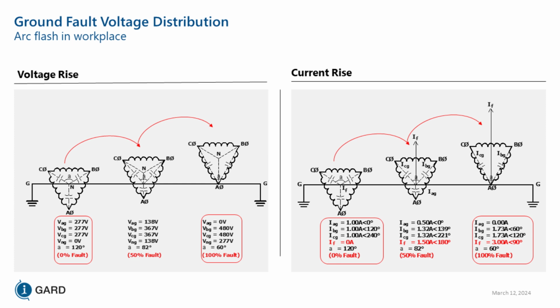Now, it's important to see in this particular diagram that we do not energize ground in an ungrounded system. You can still touch the enclosure. All we've done is shift the vector relationship with respect to ground, such that B phase and C phase are now 480 volts to ground instead of 277 volts to ground. So we just shifted the apparent neutral up 277 volts due to the ground fault. And the current you can see here is the capacitive coupling. That's something we can explain when we have another hour, how that happens.